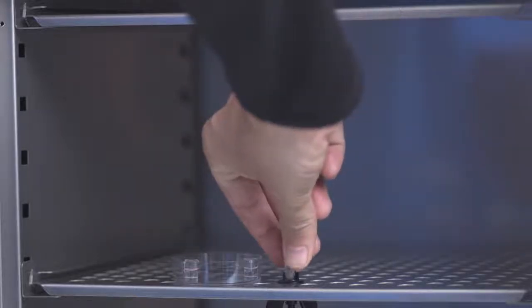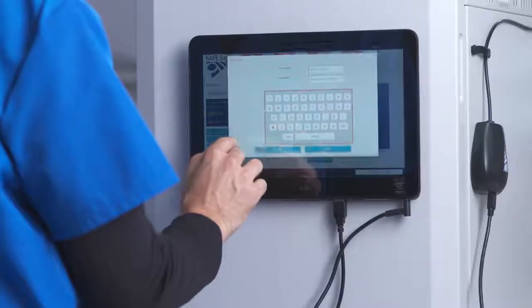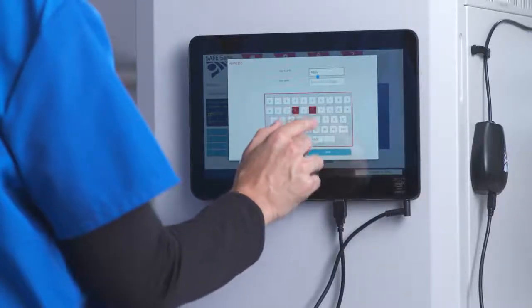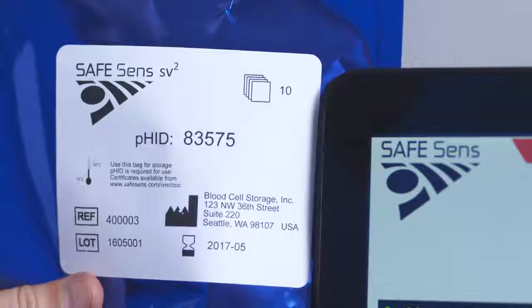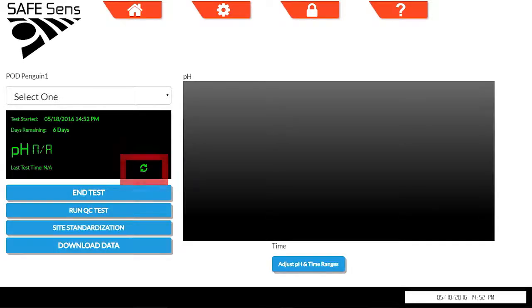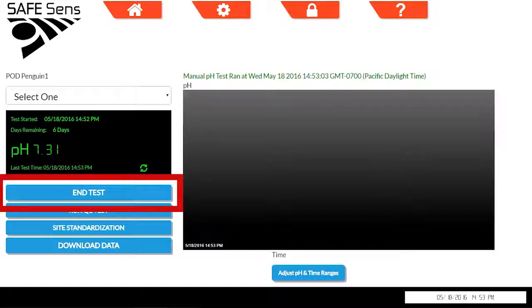Place the sensor onto the fiber probe, select the TrakPod you will use, and press the New Test button. Enter a 5-character test ID of your choosing and the pH ID that is found on the blue packaging label of the sensors. Then press Save. For the next 7 days, the TrakStation will automatically read the pH every half hour in your incubator environment. You can get a manual pH reading immediately by using the refresh button. At the end of your 7-day testing, press End Test, dispose of your sensor, and run the QC test. Then you can start pH monitoring a new sensor, which you should have prepared and equilibrated overnight.